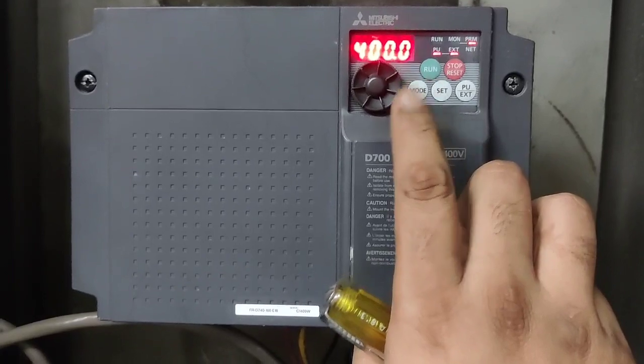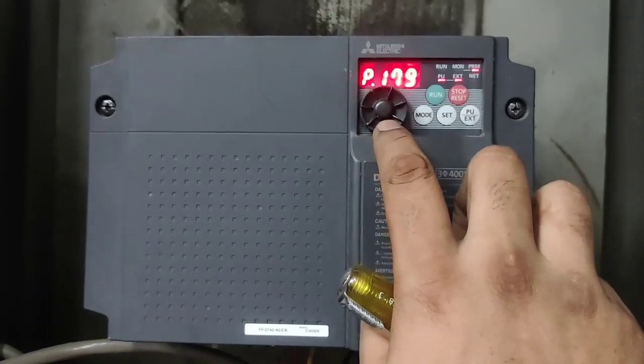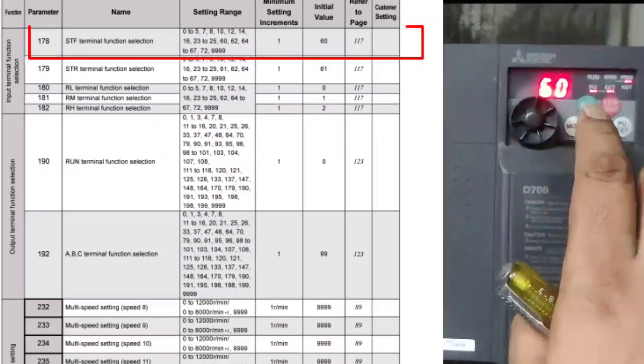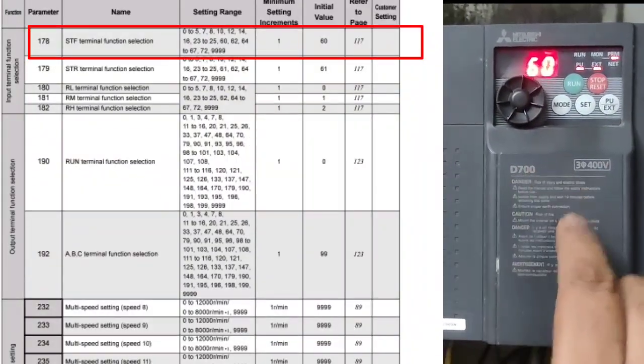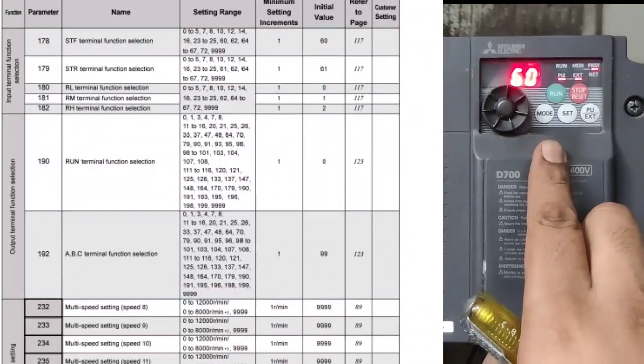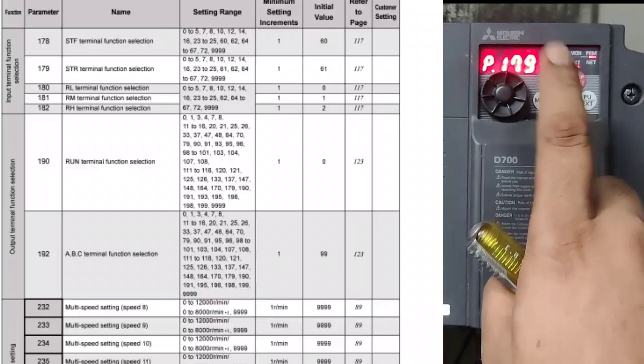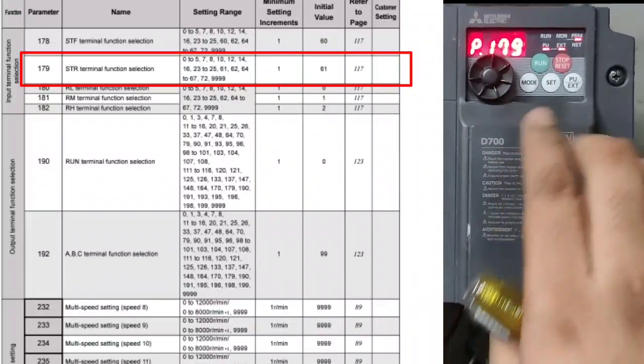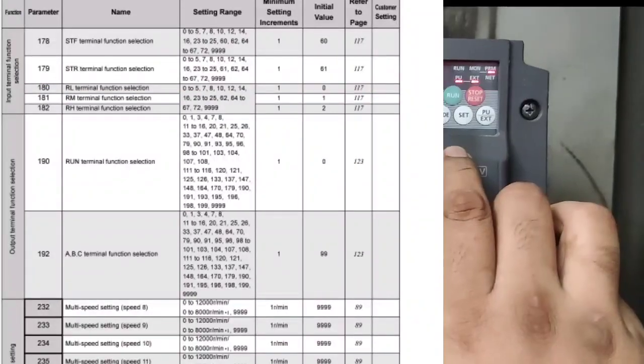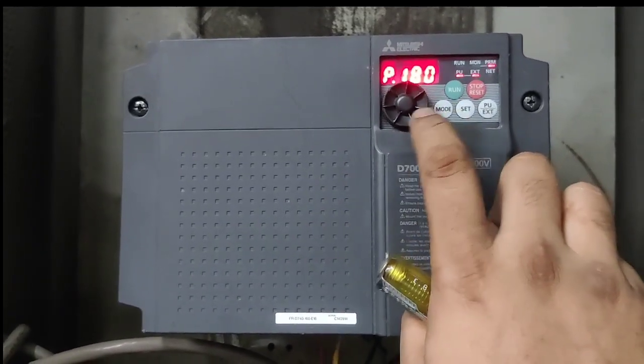For digital input selection: parameter 178 is for the STF terminal used for forward rotation. To use STF terminal for forward rotation, set 60 in parameter 178. Parameter 179 is for the STR command — if you want to use the STR terminal for reverse rotation, set 61 in parameter 179.